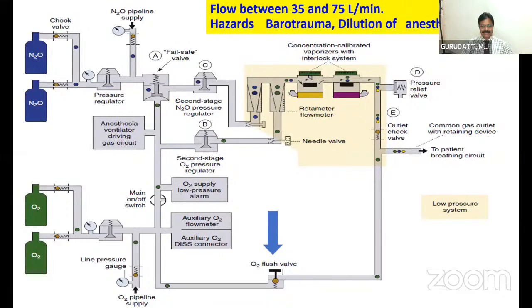So what is the function of this oxygen flush, and when are we going to use it? Especially when you are ventilating a patient with a mask and you are finding difficulty in mask ventilation because of various causes. Then there is so much leak around the face and the mask. Then you activate the flush so that you overcome this leak by an extra amount of oxygen, nearly 35 to 70 liters of oxygen flowing. So that's one of the functions of the oxygen flush.